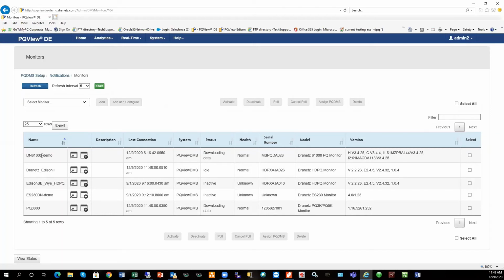They fall in the category of what we call advanced monitors. If you want to be more conservative and go with something less advanced, like the PQ3K or PQ5K monitors, which are general purpose monitors, you have a tendency to go closer to 100. So theoretically we say 100, but depending on the number of meters and meter type, you kind of have to use your judgment. The more advanced meters, you want to be a little lower; the less sophisticated meters, you can go a little higher.